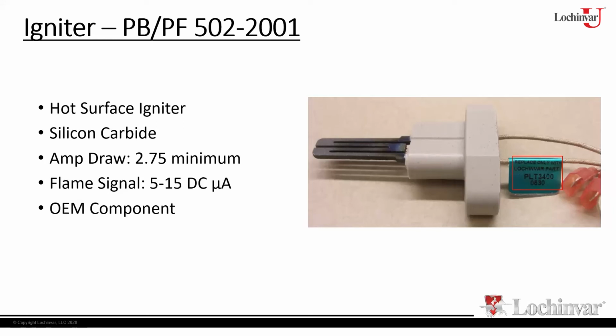And you can't just put a microamp meter in line with one of these leads, because remember, you're running 120 volts through it to begin with. And if you do that, you'll smoke your meter. So where we're looking at the microamp signal will be on the display itself on the current model. So the display will show you what that flame signal is. Okay. So hopefully that answered your question.